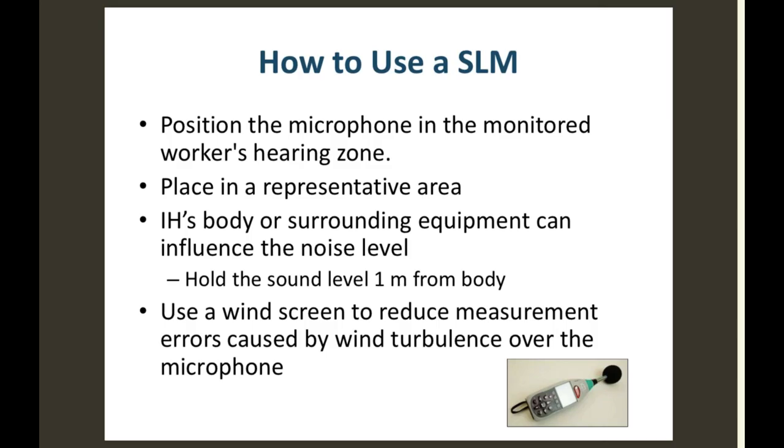First, you position the microphone in the worker's hearing zone. If you want to make a quick, short-term measurement in the worker's hearing zone, that's about a 2-foot circle diameter around his head. Then you measure. You want to hold it out at arm's length, 1 meter. You don't want to hold it close to your body because your body is going to attenuate some of the noise that might be produced.